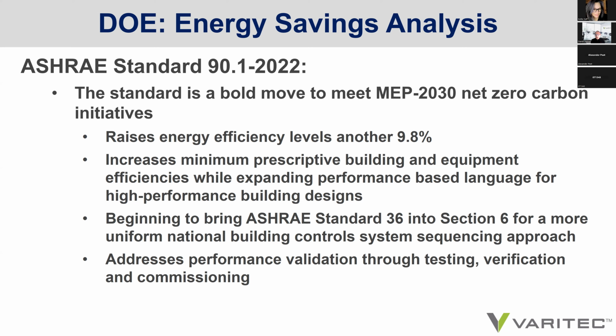It's beginning to bring in ASHRAE Standard 36, which is ASHRAE's approach for coming up with a standard to write building sequences of operation. Varitec is involved with Varitec Controls and Services today, in fact, to see how we might be a resource for Standard 36 sequences into equipment layouts, and that's a project currently under development, so stay tuned for that. But what ASHRAE is looking for is to normalize sequences of operation for buildings so that there is not this vast swing of performance depending on the design teams that write those sequences.